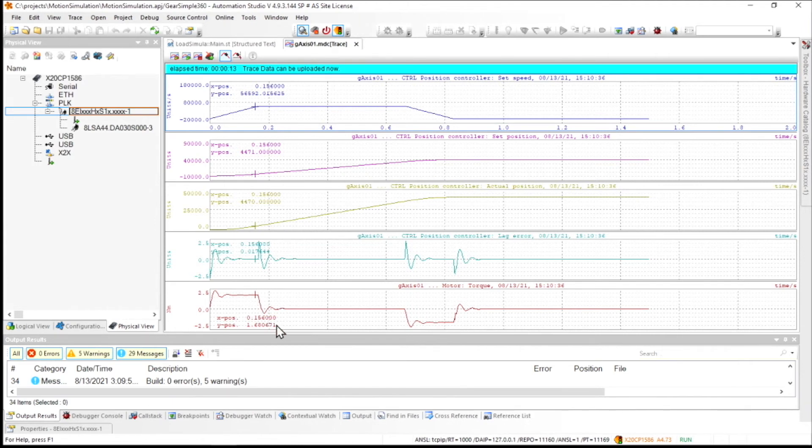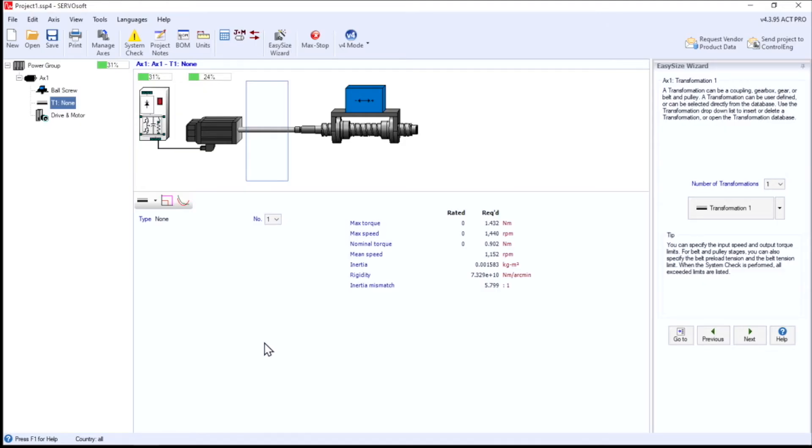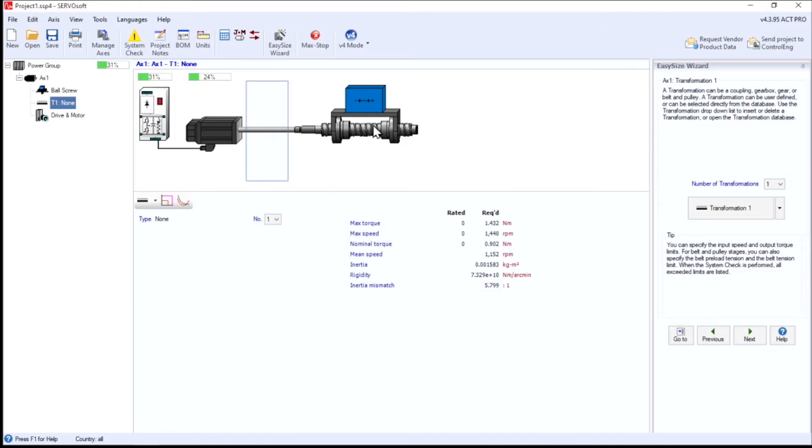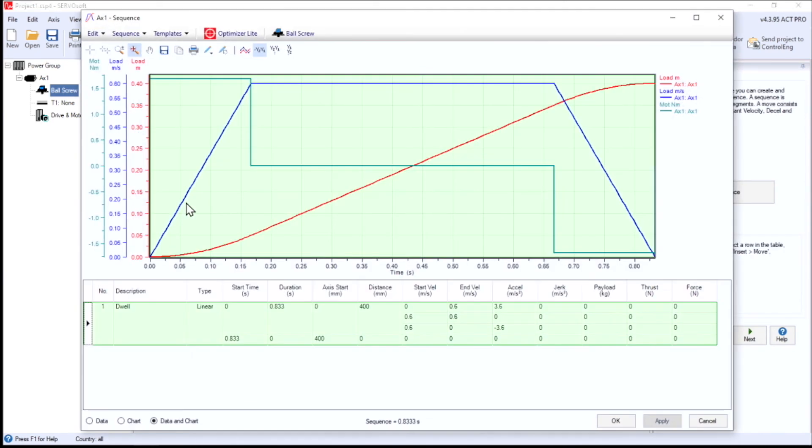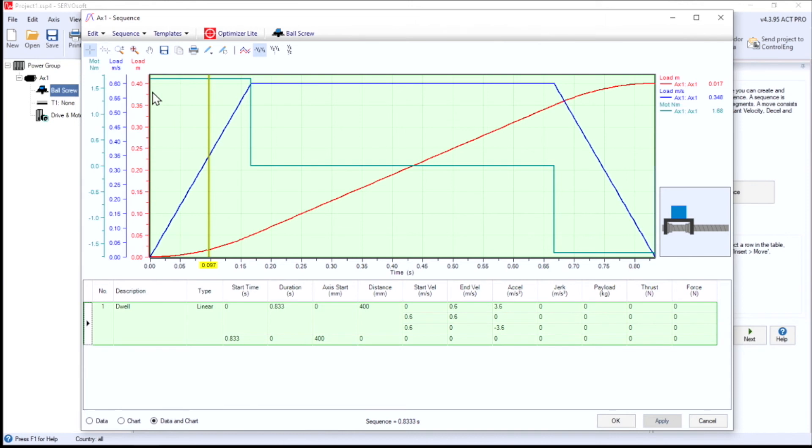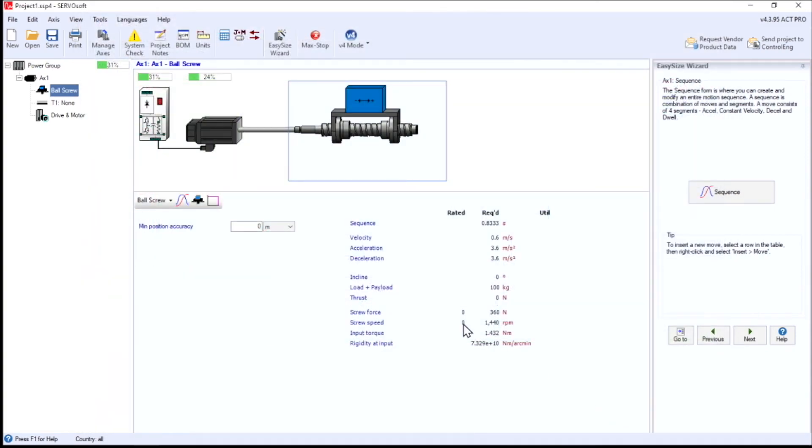Now I wanted to see if this model would actually match some of the other tools we use, so I fired up ServoSoft. It's a tool that we use for sizing here at Loop. And I made a system that had the exact mechanics with the same amount of inertia and same movement profile. And when I took a trace here, I see that the torque that's in green has the exact same torque measurement of 1.68 newton meters. So that gives us a lot of trust that the tools that we're using are modeled identically.